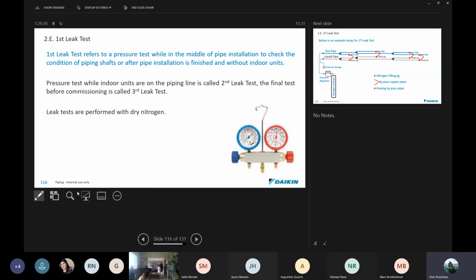What is very important about any pressure test is to log 2 things. First of all, the starting pressure and the starting ambient temperature, and then when you come to checking, you need the final pressure and the final ambient temperature. Just keep that in mind, because a lot of guys tell me they've done a pressure test, and I ask them what the starting and finishing temperatures are, and they can't tell me. So it's very, very important that they do that.